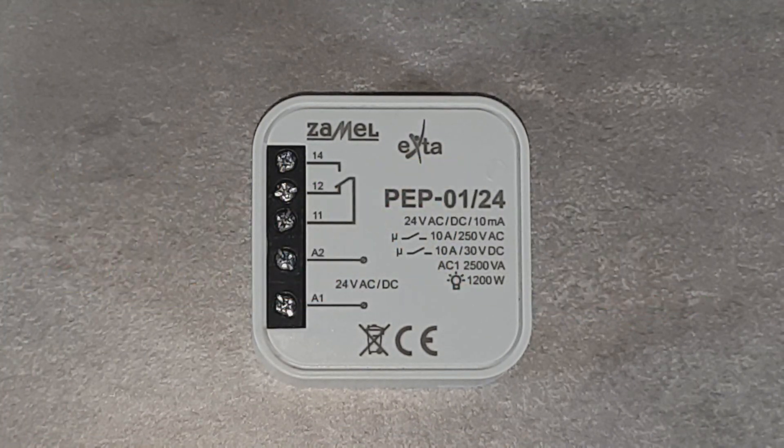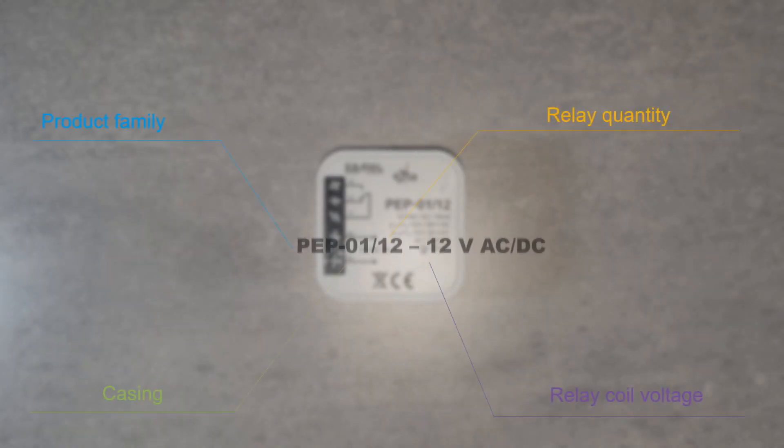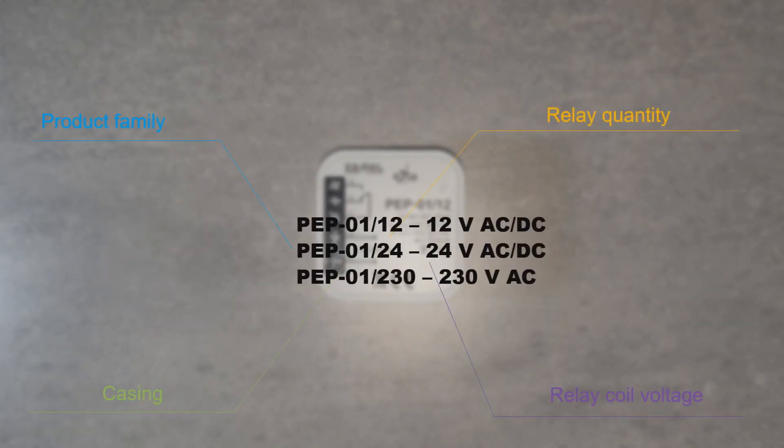The PEP-01 device belongs to the product line of universal electromagnetic relays for box installation. The electromagnetic relay, after applying the supply voltage to terminals A1 and A2 — which are the inputs of the relay coil — switches the NO-NC contacts to the ON state, and by this closes terminals 11 and 14, as long as the voltage is available on the coil. Then, normally closed terminals 11 and 12 are switched on.